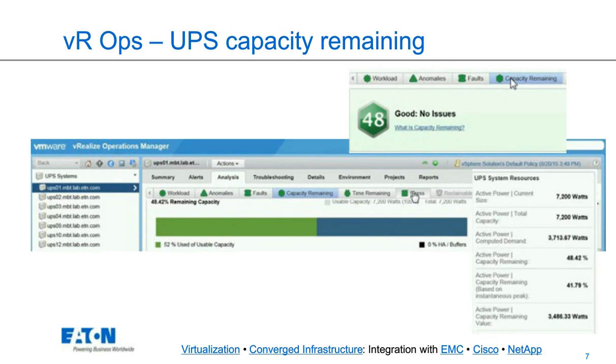The first one that we show you shows on the left side, we select a UPS, and then on the far right side, it gives you some attributes of what the UPS is. You get the total power, in this case 7,200 watts. It tells you the current demand, which is 3,700 watts, and at the bottom, it tells you how much capacity is remaining. And vROps will do the math, and it'll tell you that you have 48% left of battery capacity.